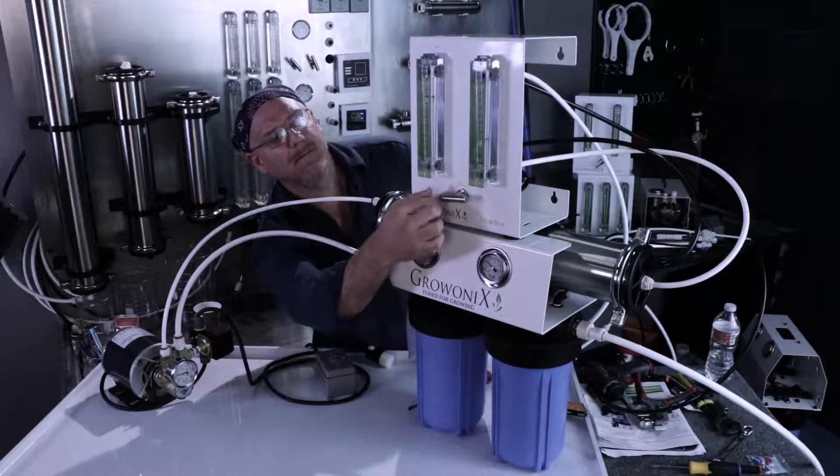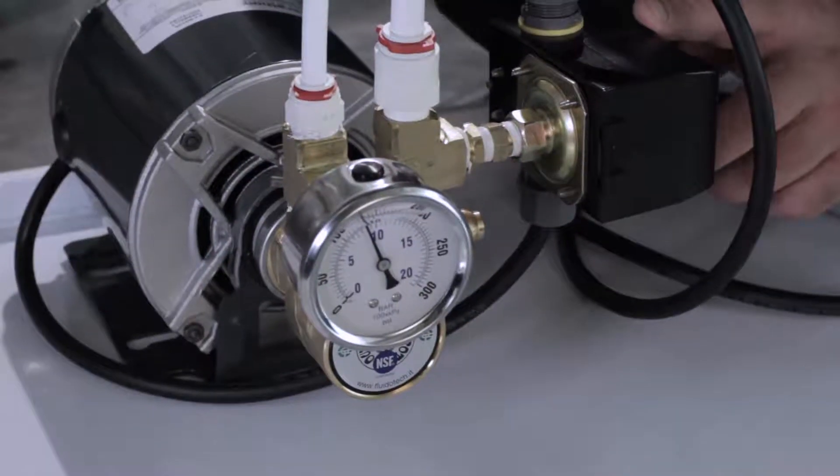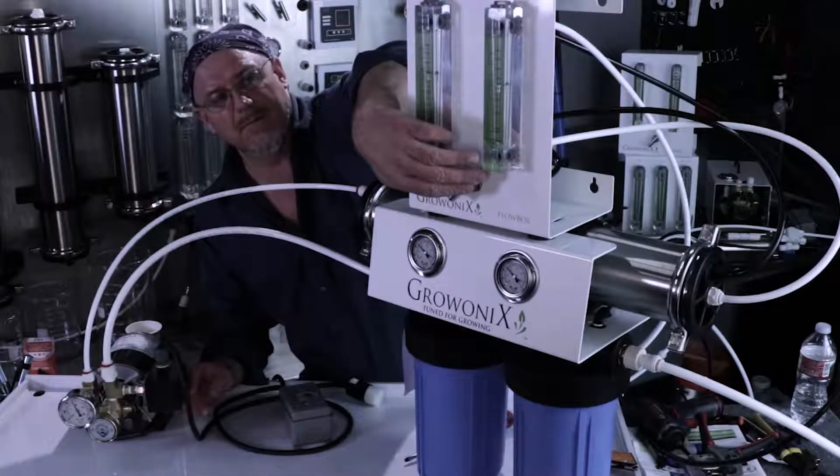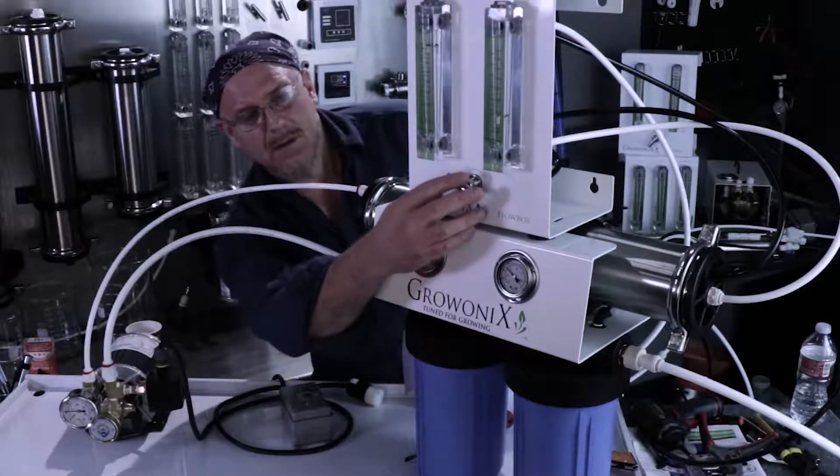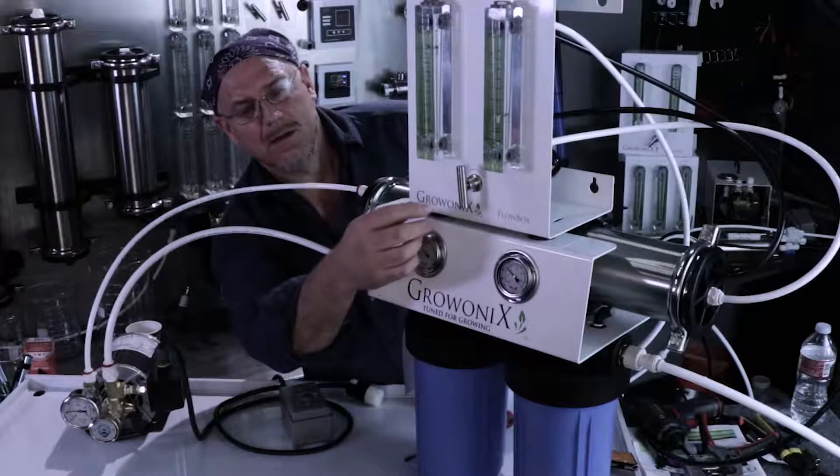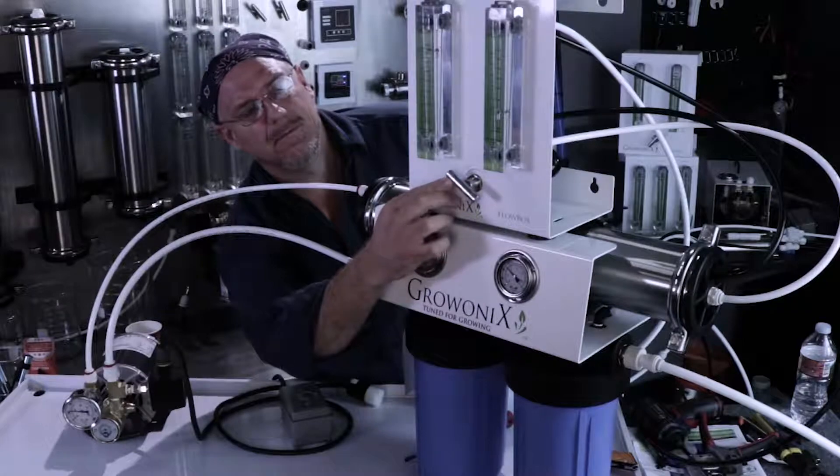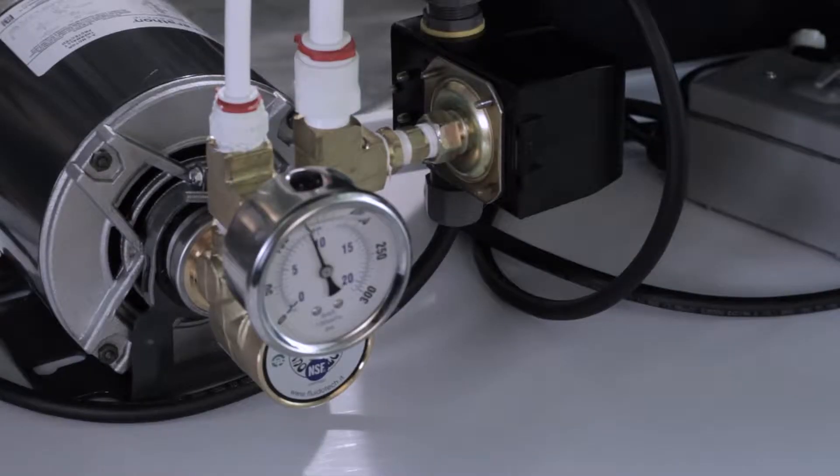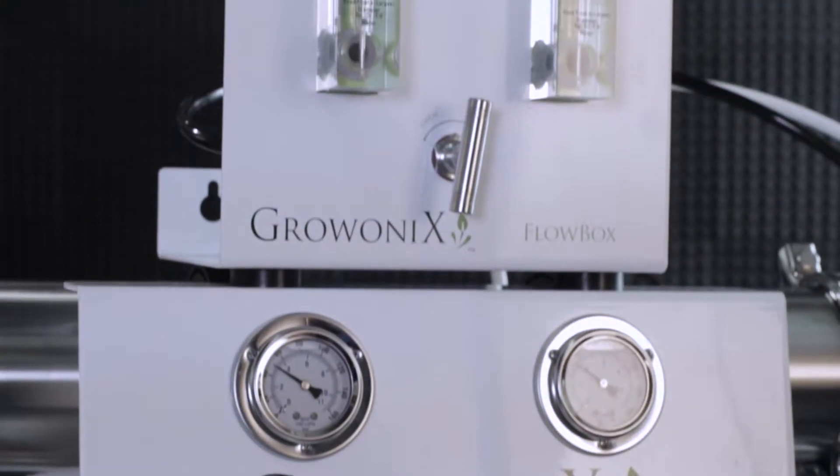One thing I want to show you: notice when you enter flush mode that the pressure on the gauge goes down. That's because more water is being allowed through the system, so the pressure goes down. When you go back to normal operation, the pressure will go back up. Every time you adjust your ratio to whatever you want to run this system at, one to one or two to one, you have to adjust your pump pressure accordingly.